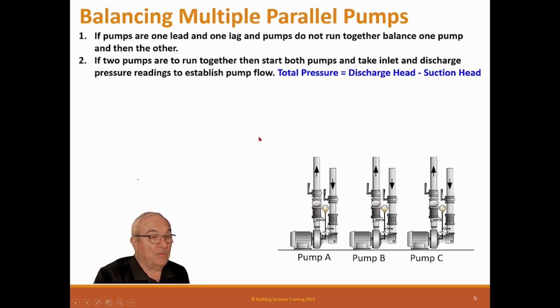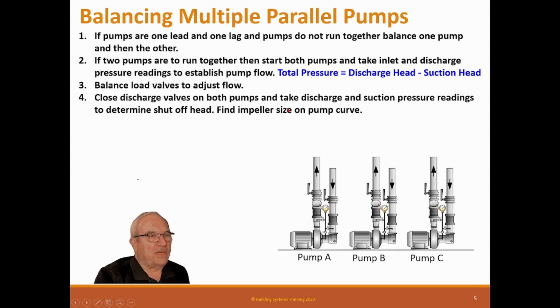Now, what if you have three pumps? Well, that means that the third pump is standby to one of the others. So you know that you have roughly 50%, 50%, and then you have a standby 50%, so you're still good for standby. You assume that you're not going to lose two pumps together. Balance the load, and then close the discharge valves on both pumps and take the suction pressure and discharge pressure. These should have the same impeller, and you can do one at a time or together. It doesn't matter, but you read the discharge head and the suction head and find out where you're at on the curve to figure out the impeller sizes.